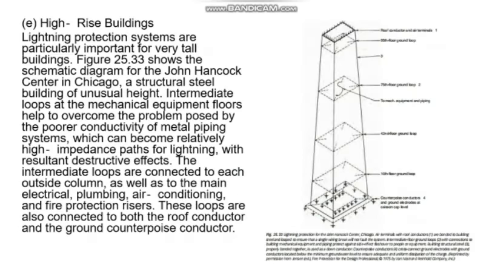Last example is the high-rise buildings. Lightning protection systems are particularly important for very tall buildings. Figure 25.33 shows the schematic diagram for the John Hancock Center in Chicago, a structural steel building of unusual height. Intermediate loops at the mechanical equipment floors help to overcome the problem posed by the poorer conductivity of metal piping systems, which can become relatively high impedance spots for lightning, with resultant destructive effects.